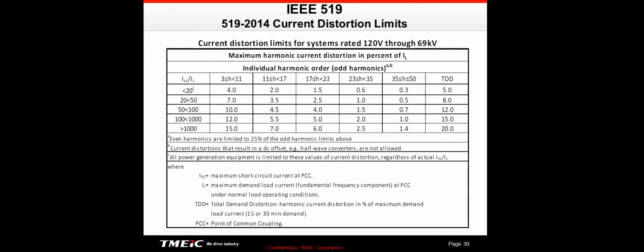Latest version is 2014. And if you look over there on the right, you see a column called TDD. That stands for total demand distortion. And basically, it is your total current distortion at your highest load during the month, or basically your load when you set your utility demand. So your current distortion could go anywhere from 5 to 20%. Typically on systems, 12 to 15% is sufficient. However, the larger the drive, the more likely it is that we're going to need better.